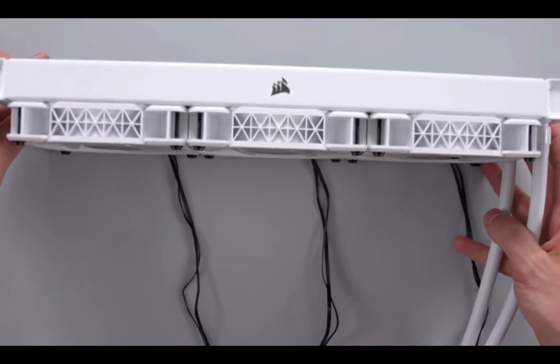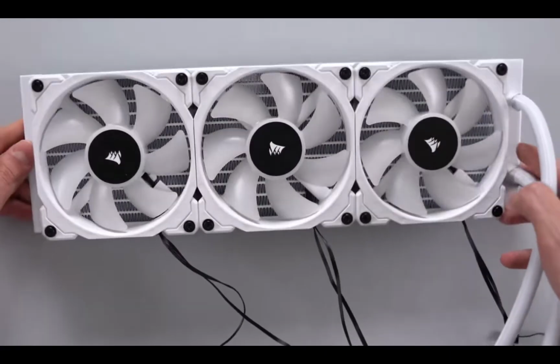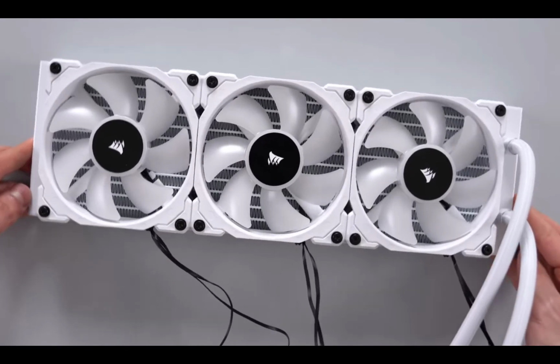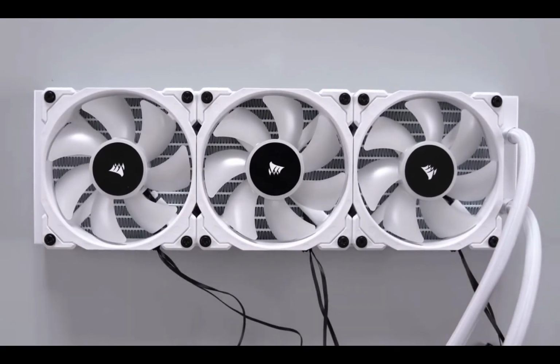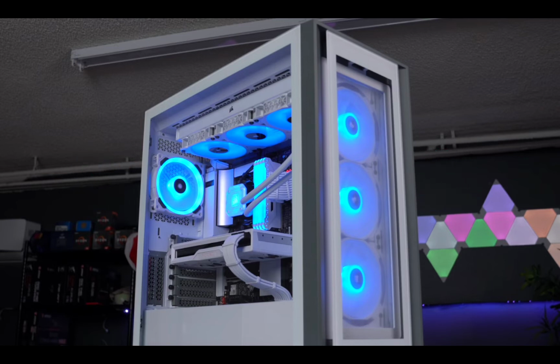A lot of fans don't have arrows on the sides. In that case, you have to look at the fan and determine the airflow direction yourself. Always remember this term: faces suck. The face of the fan is always where air gets sucked in from. So if the face is on the right side, the airflow goes right to left. If the face is on the bottom, the airflow goes bottom to top, and so on.